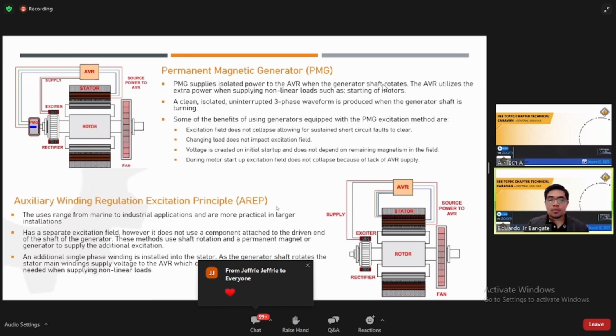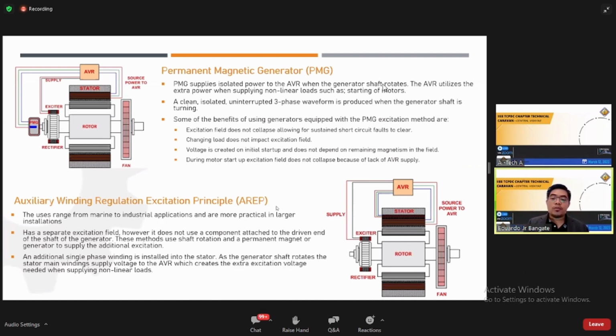Next. Now we have the permanent magnet generator. Generators equipped with permanent magnets are among the most well-known separately excited methods. A permanent magnet is mounted on the drive end of the generator shaft. Okay? So a clean, isolated, uninterrupted three-phase waveform is produced when the generator shaft is turning. Some of the benefits of generators equipped with the PMG excitation method are: the excitation field does not collapse, allowing sustained short circuit faults to clear. Changing loads does not impact the excitation field. Voltage is created on initial startup and does not depend on remaining magnetism in the field. During motor startup, the excitation field does not collapse because of lack of AVR supply.